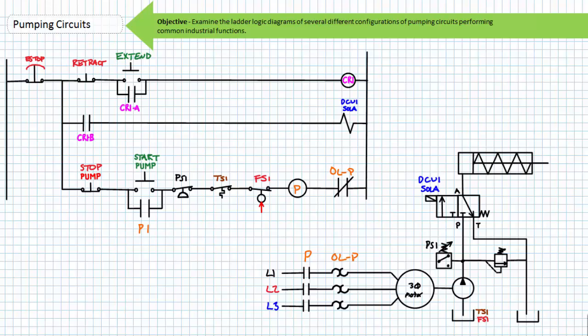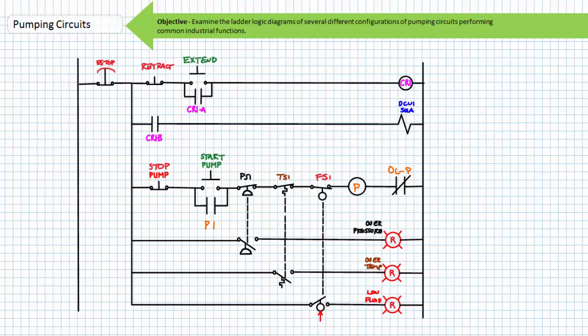Notice there's no feedback, and an operator is going to scratch their head and say, "Don't work," on their maintenance requests, giving you, the technician responsible for returning this pump to service, no clue as to what to expect. It is for this reason ladder logic can also be used to perform diagnostic services.